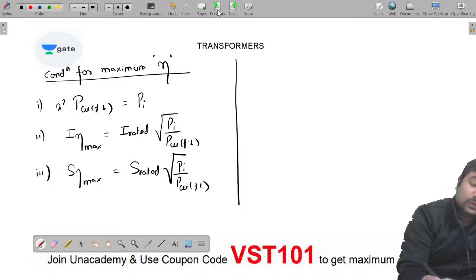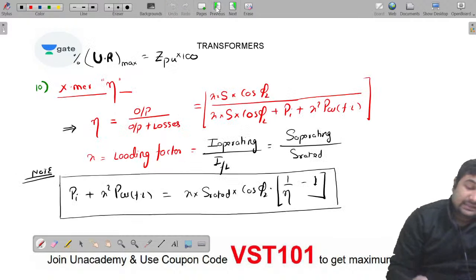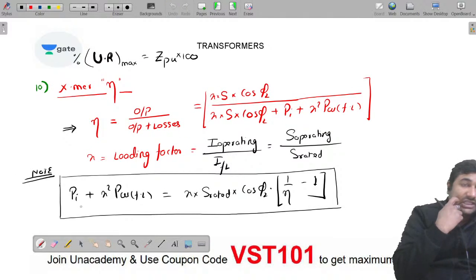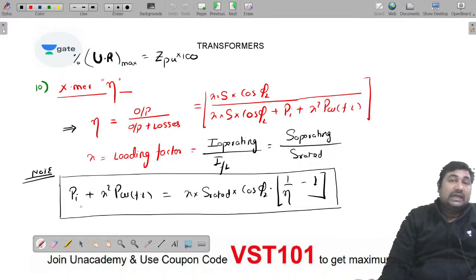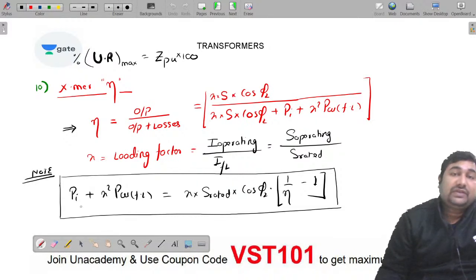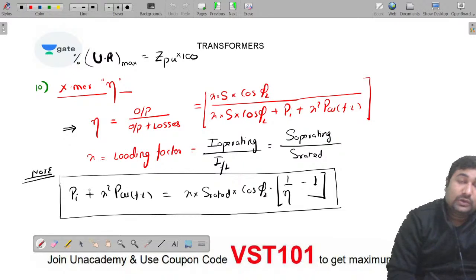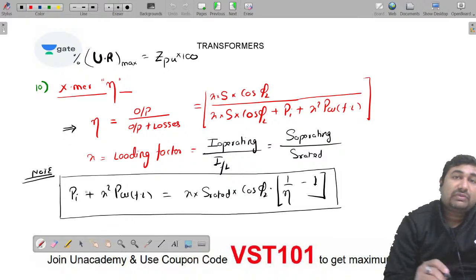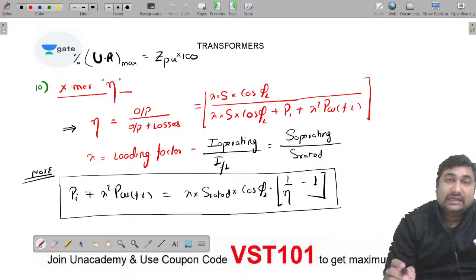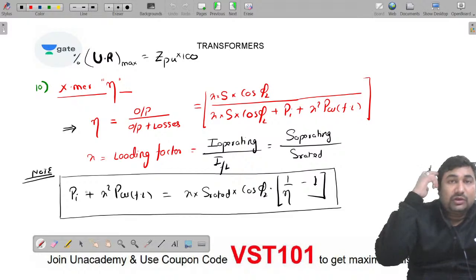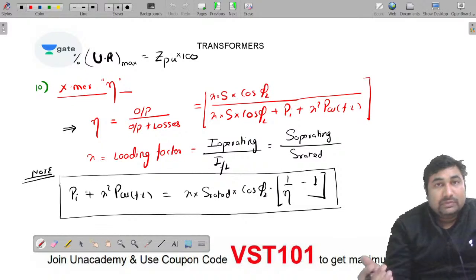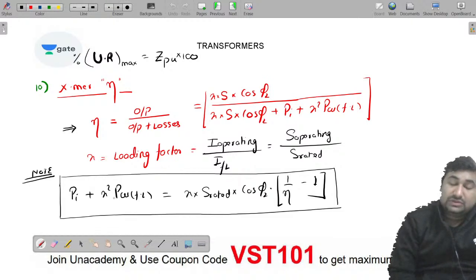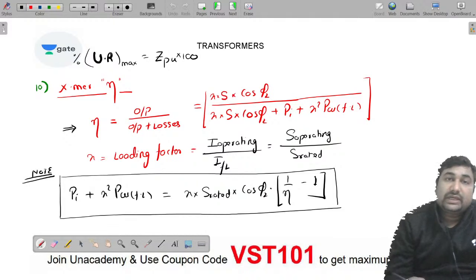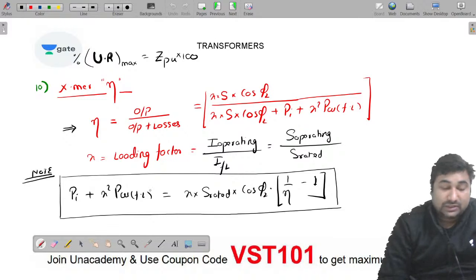Suppose we have a transformer with an efficiency of 98% at 3/4 of full load, meaning at loading factor 3/4, efficiency is 98%. Again, the same transformer has an efficiency of 99% at full load unity power factor, so the loading factor equals 1. You can use this formula to form two different equations and solve them to find Pi and PCUFL of the transformer. Is it okay?